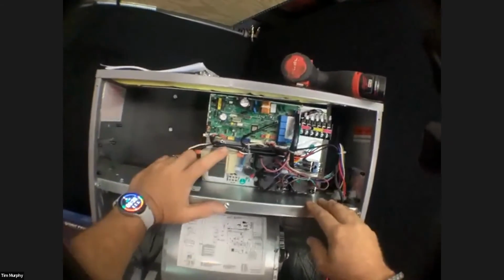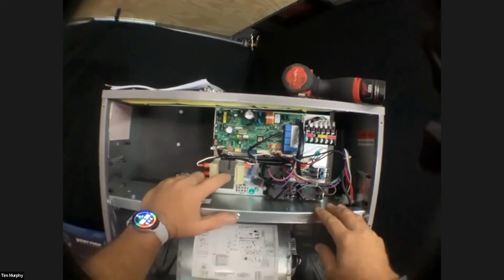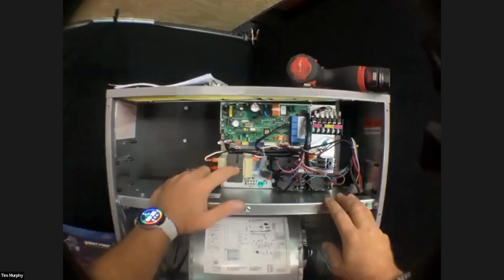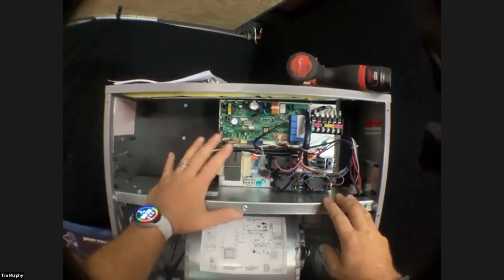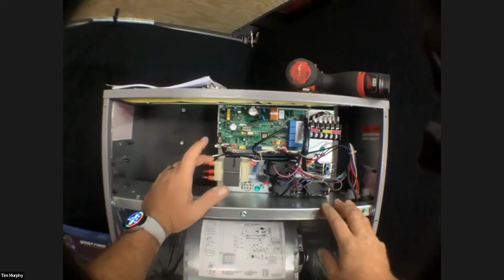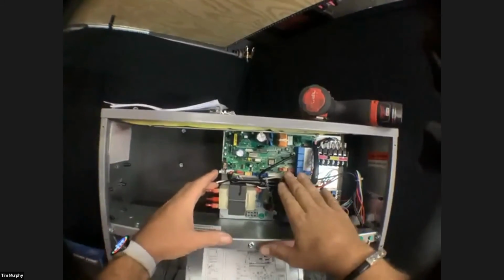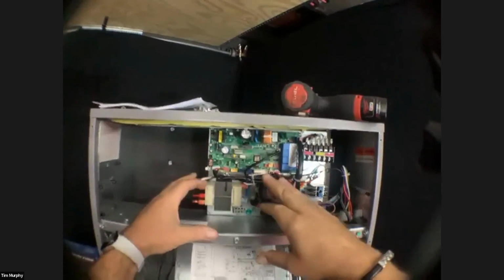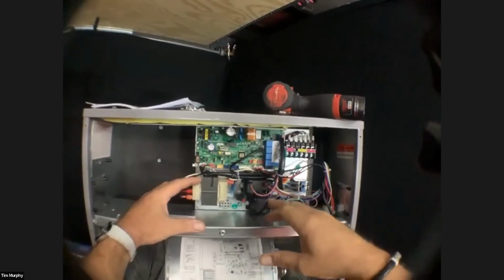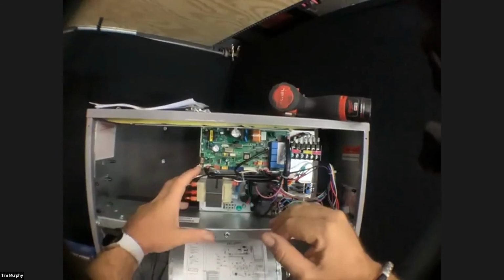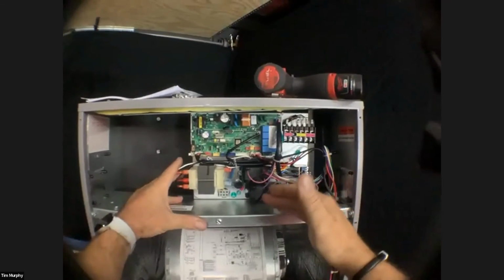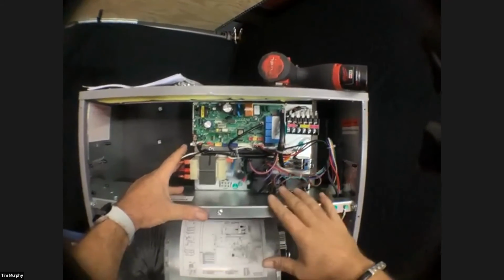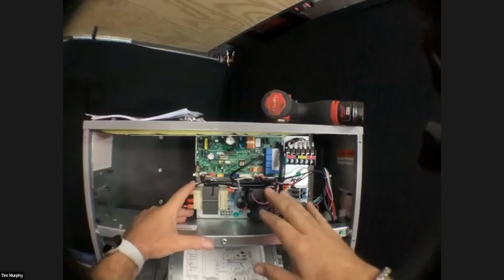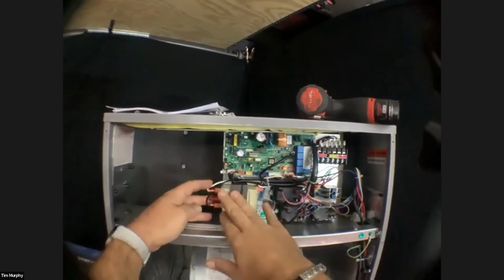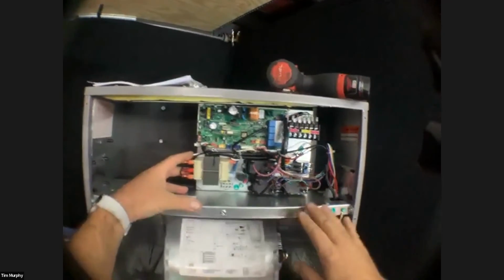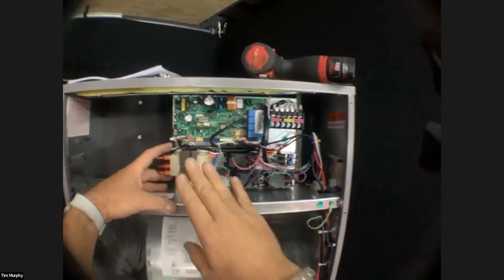One thing to note, you're not going to want to break red on this in order to wire a float switch. If you're installing one of these, do not break red on this to install a float switch. You're going to want to either tap into the board and activate that on the menu of the advanced controller, so that if you do get an overflow call, it's going to give you an error code that's an overflow safety switch trip. If you wire it into this, it's just going to create all kinds of problems for you. So you definitely don't want to wire that on red.